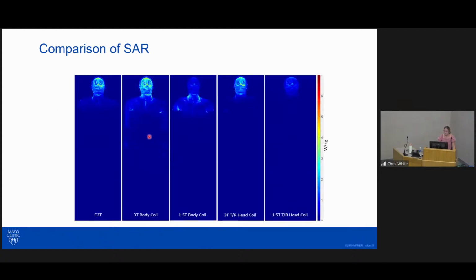This shows the coronal maximum intensity projection of SAR in watts per kilogram across these 5 different coils. On the left is the compact 3T, and the next 2 columns are the 3T and 1.5T body coil for a whole body scanner. Here we can see there's an increase in SAR in the chest region compared to the compact 3T. The next 2 columns are the 3T and 1.5T TR head coil for a whole body system, and this shows that the TR head coil largely limits SAR to the head and neck region compared to the compact 3T and the body coils.